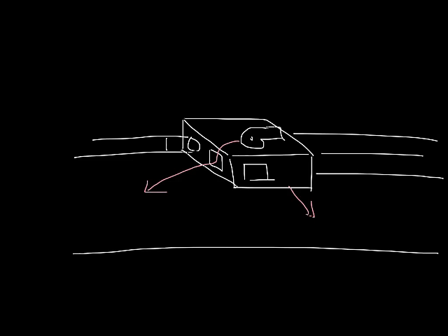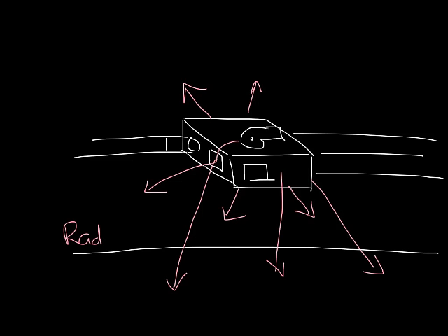So let's draw a fan box. That's our induced air inlet. Here's our ductwork going in, ductwork going out. Put a little control box on it, and there's our ceiling. So fan boxes have a motor-blower combination which creates sound in the box. This sound can travel out the induced air inlet and into the ceiling plenum. Then the radiated sound can pass through the ceiling plenum into the space. The discharge sound is before it comes out of the box, through the ductwork, and then into the space.